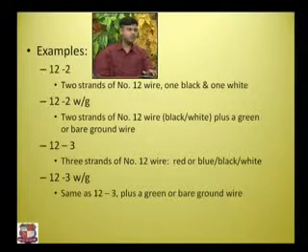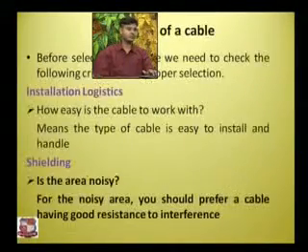If it is written 12/3, it will be three strands of number 12 wire: red or blue, black and white. If it is written 12-3 W/G, it is the same as 12/3 but plus a green or bare ground wire.